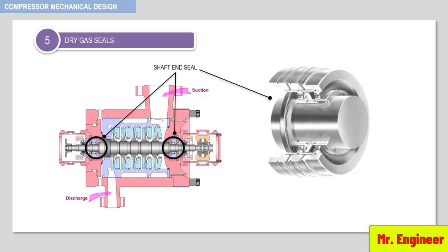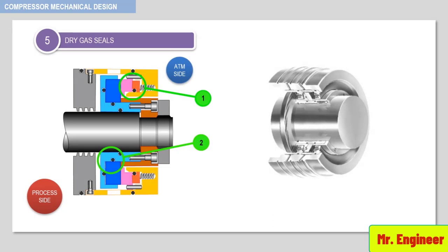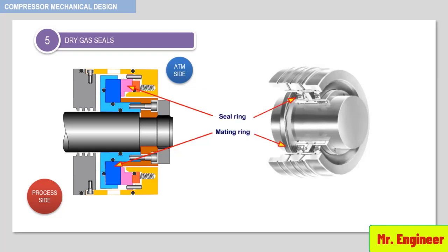A typical dry gas seal consists of two parts: a spring-loaded stationary seal face sealed by an O-ring, and a rotating seat. The rotating and stationary faces act against each other toward providing sealing action. The sealing faces of the seal ring and mating ring maintain each other without contact, resulting in high operational reliability and long service life.